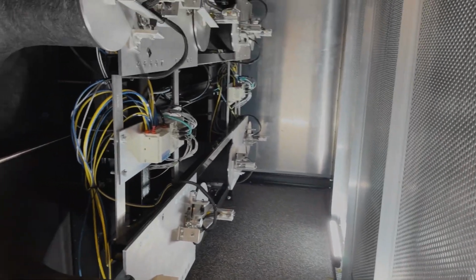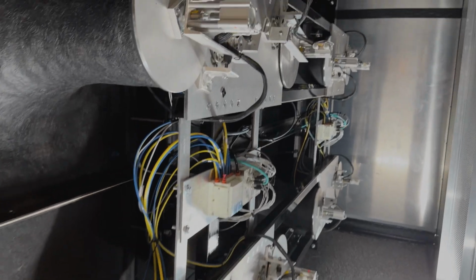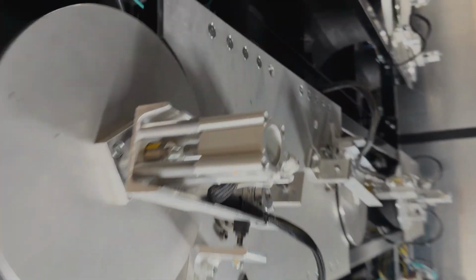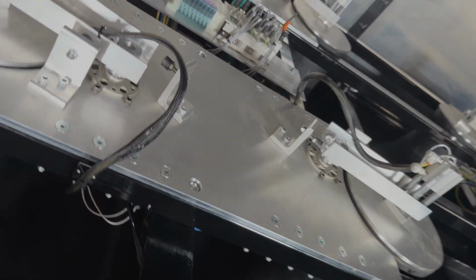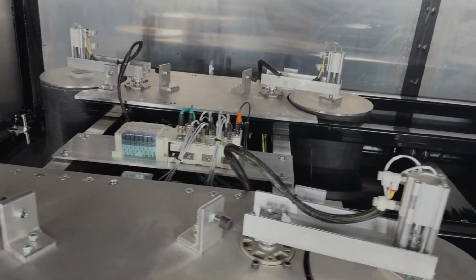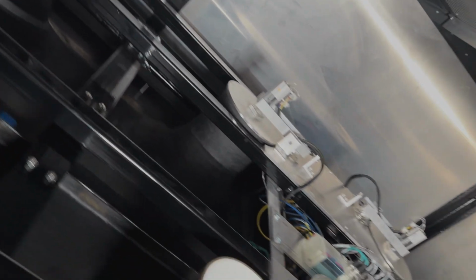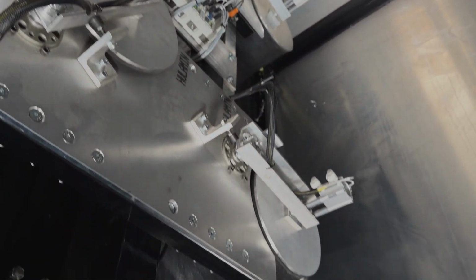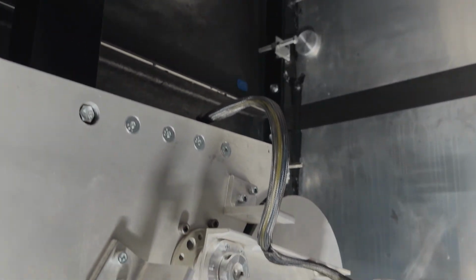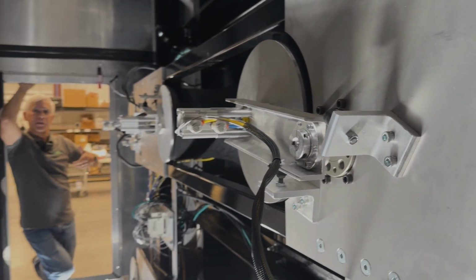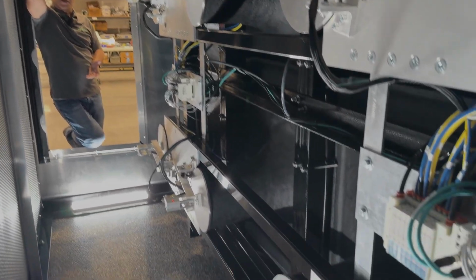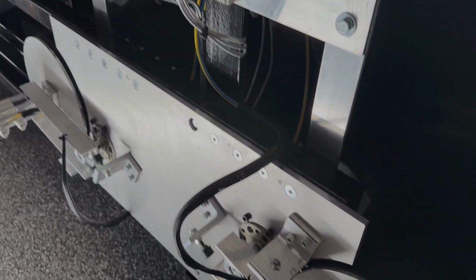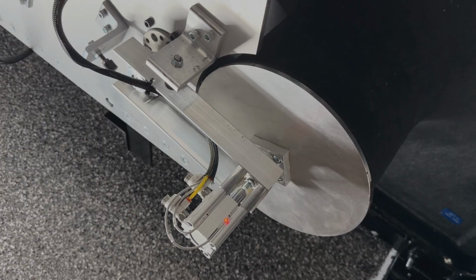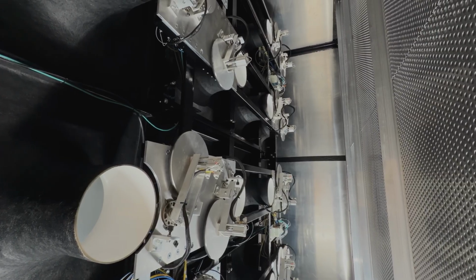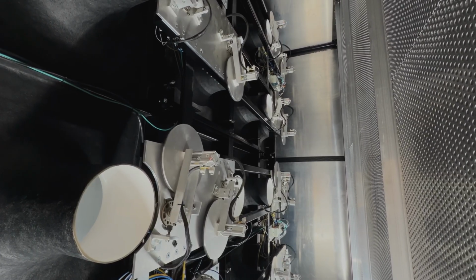On the left, it gets a little more interesting. What we have here is one of the most unique features of this airflow tunnel, of any airflow tunnel, in fact. Because we need to collect so much data, and because we're going to go over such a wide regime of airflows, 2,000 to 70,000 CFM, we're going to be changing the amount of airflow a lot, which means to measure that airflow correctly, we need to change the nozzle configuration a lot. And so what we're seeing here is the backside of the nozzles and the actuators that will let us automatically change the number of nozzles we have open or closed as we're progressing through the test.